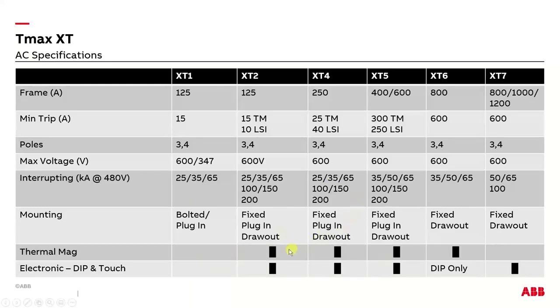But the interesting point is that we can get our LSI breakers down to really low trip values, whereas in the past we had some difficulty because we had to go to bigger frames. So we had to use a 600 amp frame to get LSI, whereas that was in Spectra world. Now in the new world that we're in with Tmax, we can have a 125 amp frame breaker and we can dial it down to 10 amps with LSI. So that's a big jump, because a breaker cost is proportional to frame size. So a 125 amp frame is always going to cost a lot less money than a 600 amp frame. So now we have that technology available across a much greater span of breaker sizes.